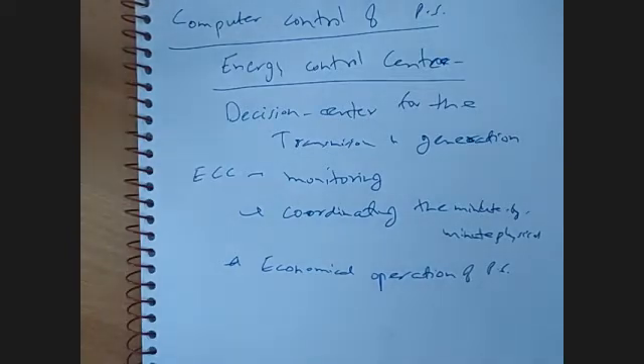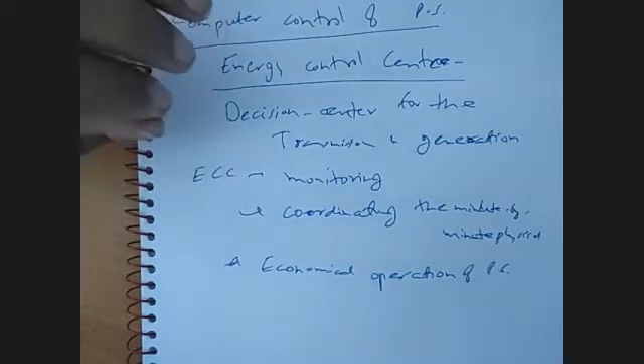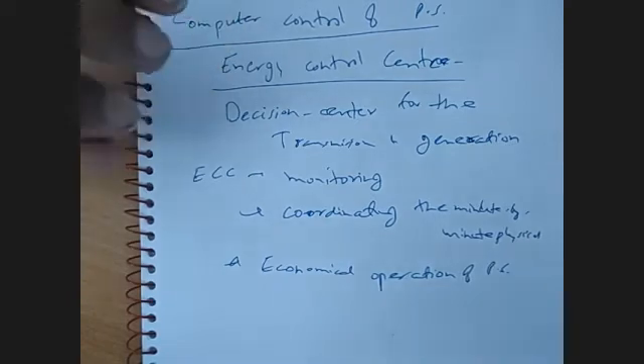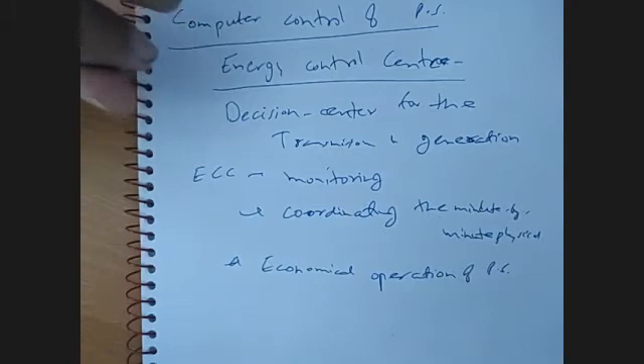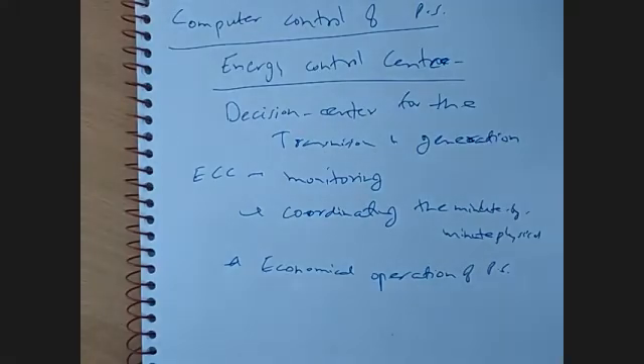So they will be monitoring the complete power system. That means they will be continuously monitoring what is the generation by each generator, what is the voltage of various parts, what are the currents flowing in the system. They will be regularly coordinating the minute by minute physical and economical operation of the power system. That means it will command the generating units to generate power so that the power system will be working in the economical operating zone, because the generating units have different characteristics. On the basis of their characteristics, their generation capacity will be decided to meet the particular load demand.